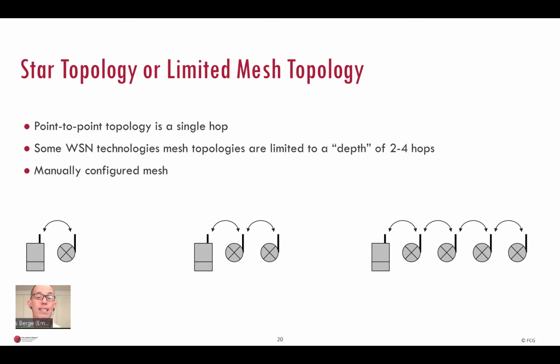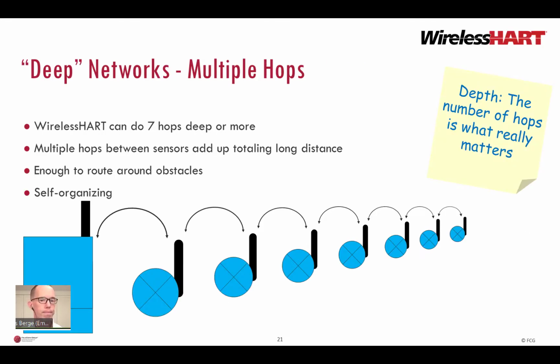Anyway, point-to-point topology is only a single hop. Some wireless sensor network mesh topologies are able to do 2 to 4 hops, but that must be manually configured. This is not sufficient to go around large obstacles, so be careful. Multiple hops between WirelessHART sensors add up from sensor to sensor, totaling long distance or greater depth from sensor to gateway, even in a plant full of steel.